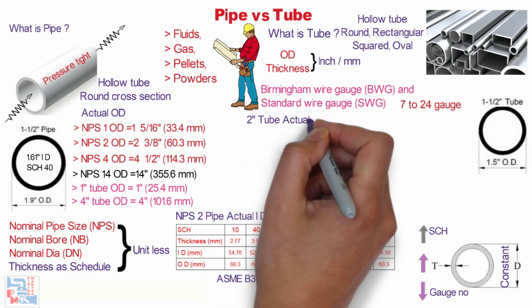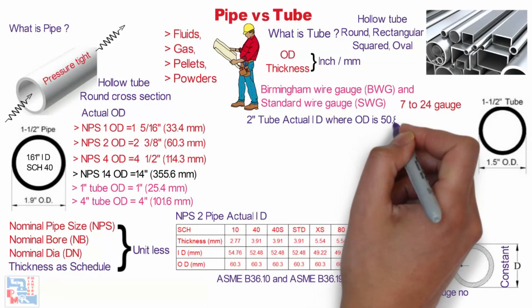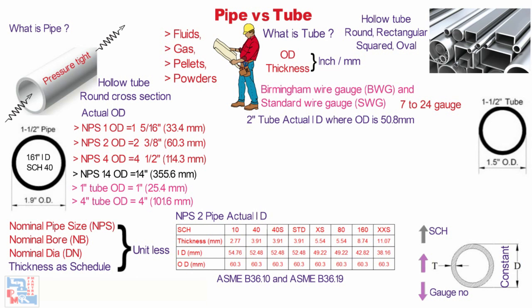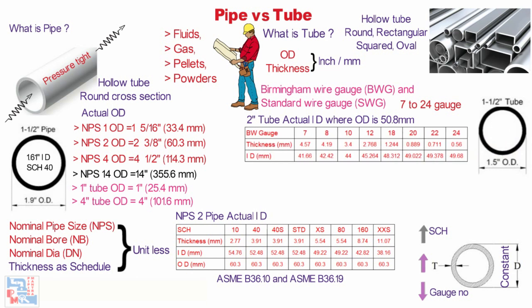You can see these tables for 2 inch tubes showing variation in inside diameter according to gauge variation, where OD is 50.8 mm constant. This table shows the variation based on Birmingham wire gauge. For example, BWG 7 gives a tube thickness of 4.57 mm, resulting in an ID of 41.6 mm. For BWG 12, thickness is 2.768 mm giving an ID of 45.264 mm. For BWG 24, thickness is 0.56 mm giving an ID of 49.68 mm.